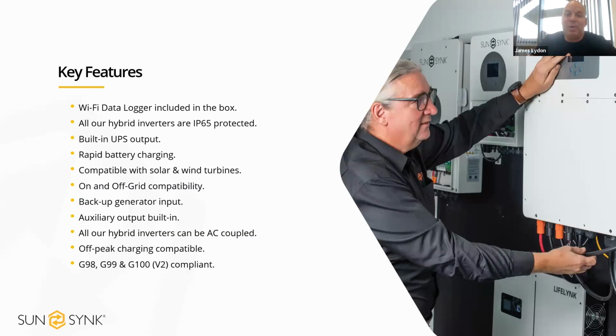So we've got 12 different points that can be set on the inverter to say, okay, at this voltage, request this much current, and then at this voltage, request this much current. We do that in 12 different stages. Obviously, as we request more current, that puts more of a load on the turbine, which in turn generates more power. So, that was a long-winded way of me saying that our inverters work with wind turbines.